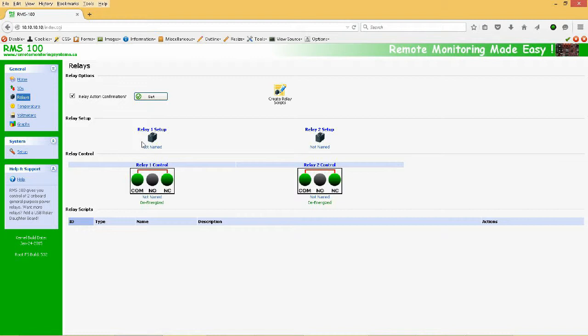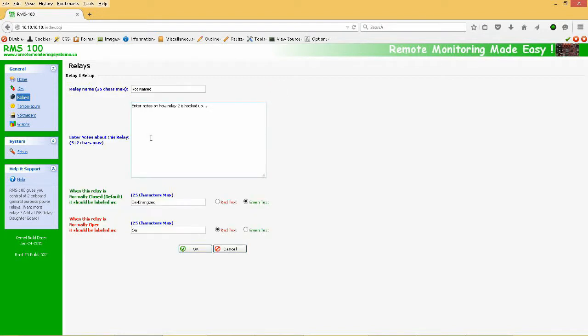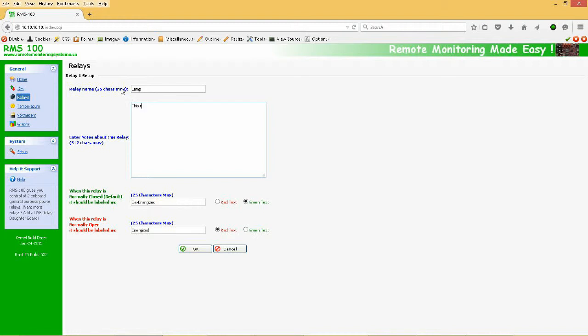For now, let's name Relay number 1 by clicking on the Relay 1 setup icon. So let's name this Relay Lamp and give it a short description. Now down here, we can describe the on and off states of the Relay. When the Relay is de-energized, the common and normally closed terminals are connected. We will call this state off and give it red text.